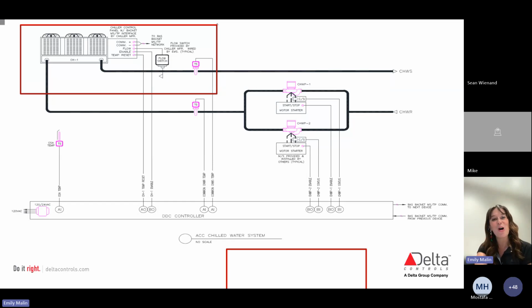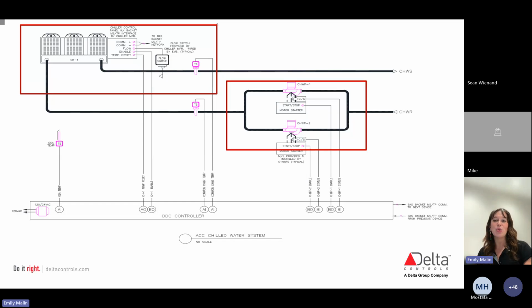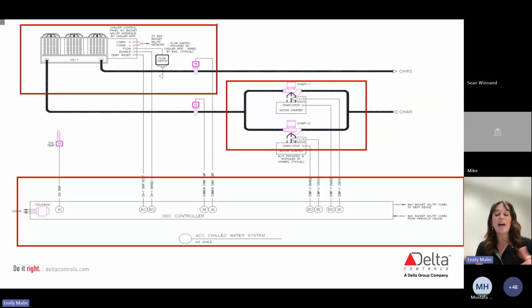But we're going to continue to move along, and we're going to get into our temperature sensors as well as our chilled water pumps, excuse me. So basically what we're looking at here is our chilled water pumps. It looks a little bit different than in that boiler diagram that we saw, because in this scenario, we don't have any VFDs on here. So right now, if you look down at the bottom, where we'll look at next, we're just looking at binary inputs and outputs on our pumps. All we're looking at is seeing if the motor starter is on, if the motor starter is off, or the status of that pump, whether or not it's on or off. And so that's what's really on that bottom level there.